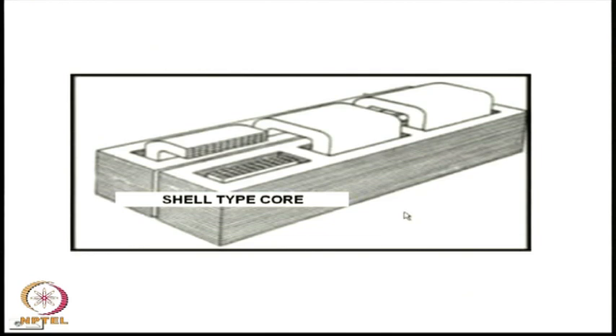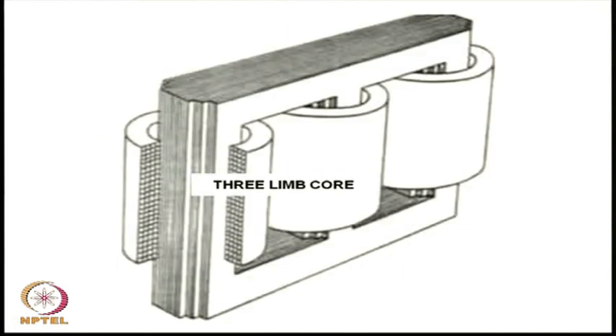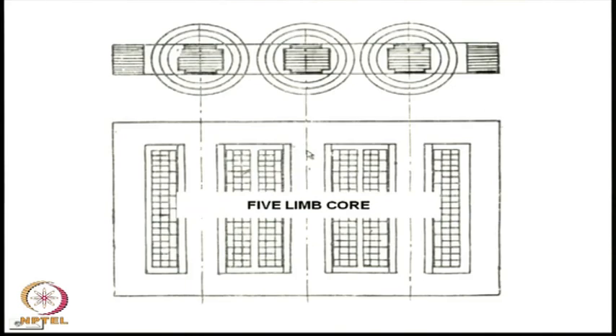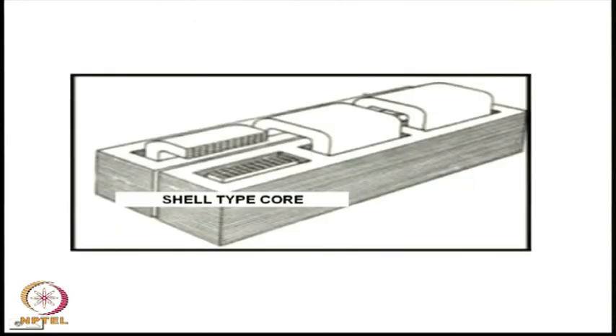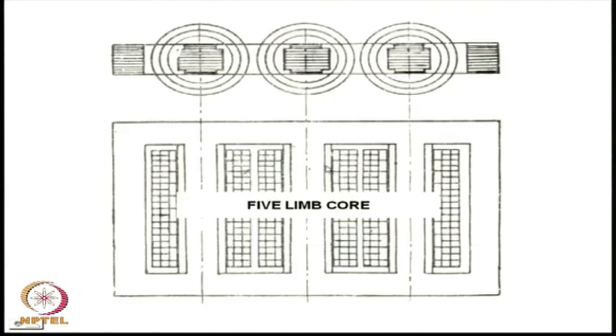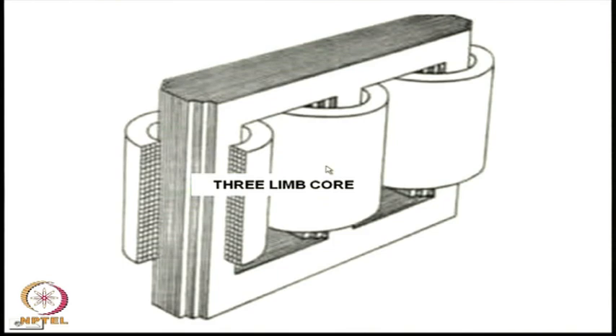There is another construction. Incidentally, this construction and the next, these are called core type transformers. There is a different construction which is called the shell type transformer, in which case the three phases operate on completely separate magnetic circuits and they operate independently of each other. However, for most three phase power transformers, the three limb construction is the most common, and that is what we will assume in our discussion.